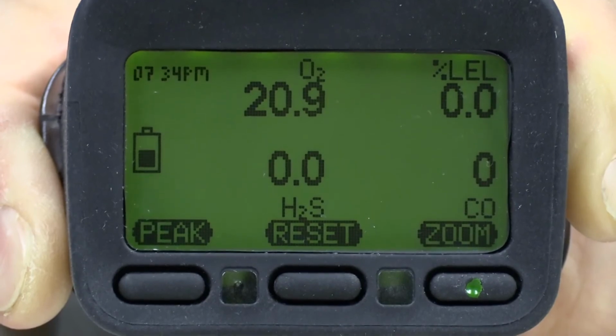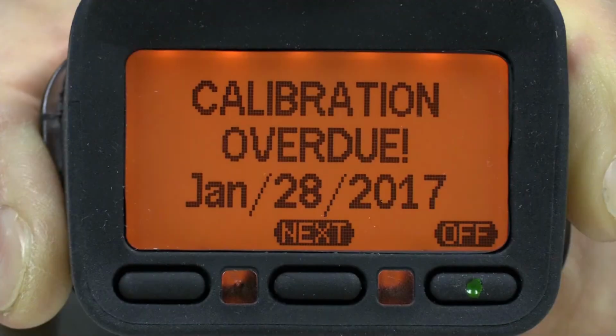A calibration due warning is displayed if any sensor has not been successfully calibrated within the required calibration period. The calibration due interval can be programmed by the instrument user, or it can be programmed at the factory or by the distributor. Warnings can be acknowledged by pressing the next button, in which case the instrument continues with the startup sequence.